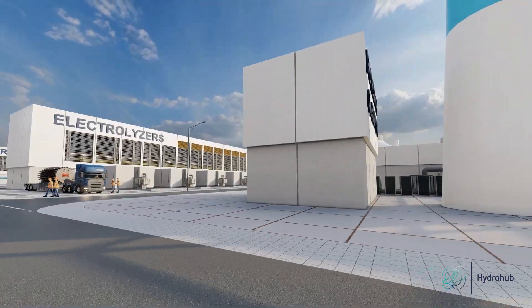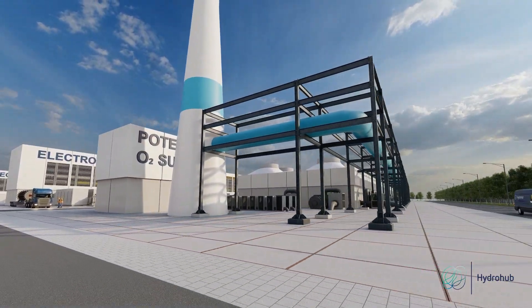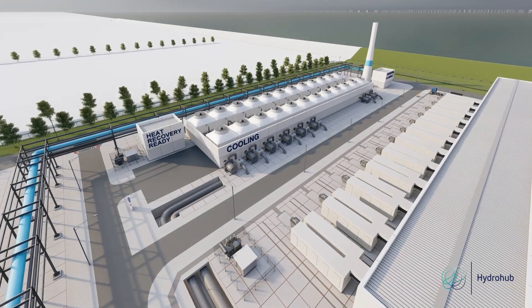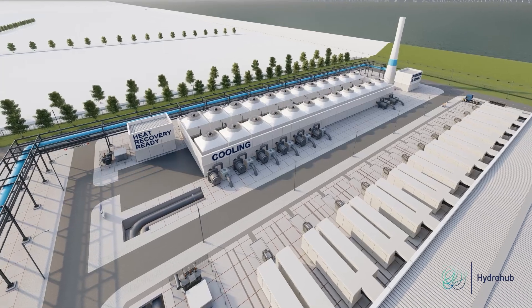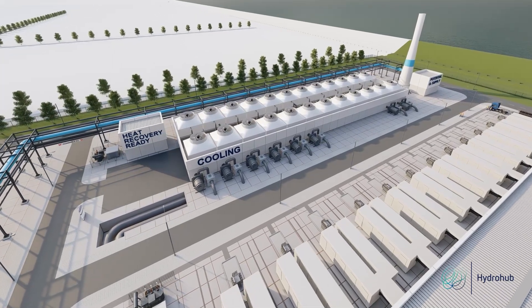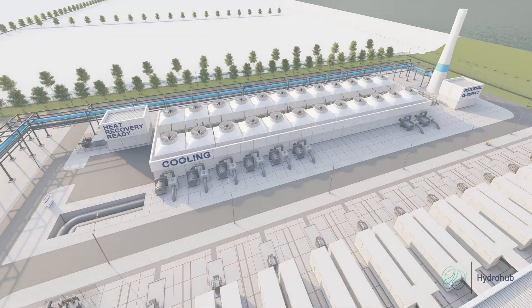As the efficiency of electrolysis for new stacks is 80%, 20% of electricity supplied is transferred into heat. There is a separate cooling water system for the heat exchangers in the recirculation loop of the electrolysers, allowing for future heat recovery and supply to a district heating network.